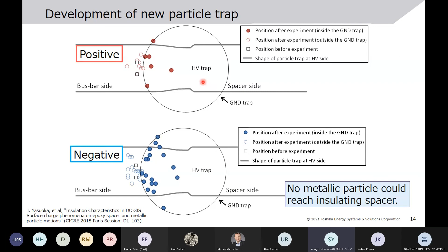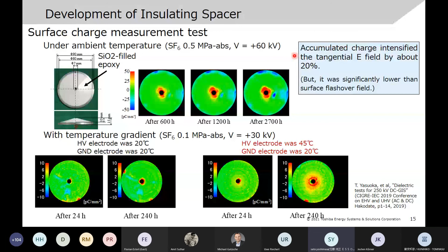And also we performed a surface charge measurement test. We prepared silicon dioxide filled epoxy like the photo shows, and we observed the accumulated charge on the surface of the spacer. So the upper side is under ambient temperature, and the lower side is with a temperature gradient between the electrode at the center of the epoxy and the perimeter part of the epoxy. So finally, we found the accumulated charge distribution on the surface, and this accumulated charge intensified the tangential electric field by about 20%, but it was significantly lower than the surface flashover level.